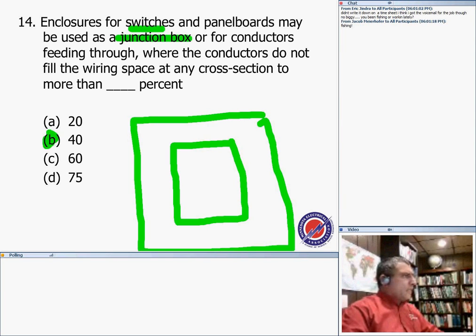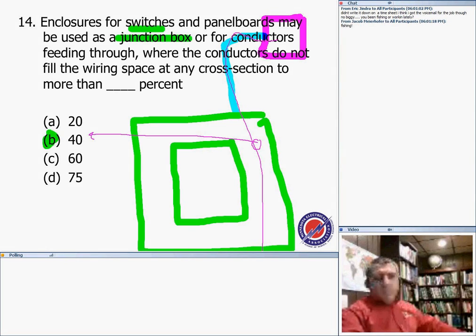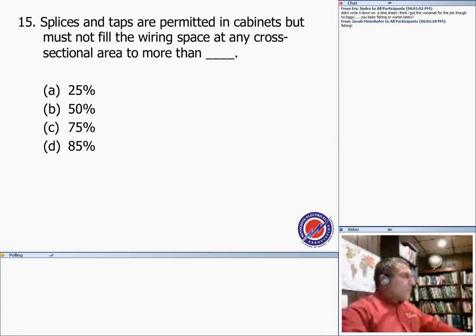If I have a switch here and a lighting fixture right here, and because I'm lazy and I don't want to go through another J box, I pipe that switch to the light, and I pipe from the switch to the panel, and the panel to the light, and then I grab my conductors, my friends, and off I go with my conductors through the conduits all the way to the box. Is it okay? No problem, as long as you don't fill it more than 40%. Any questions about this? I think we emphasized it when we were going through it. So there, number 14, number 15.